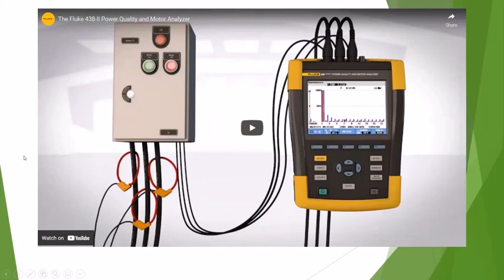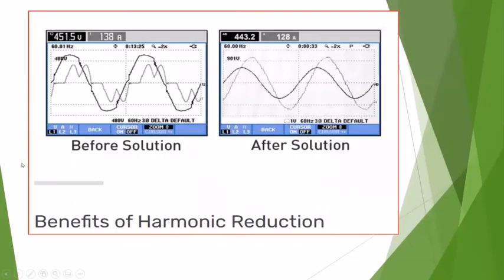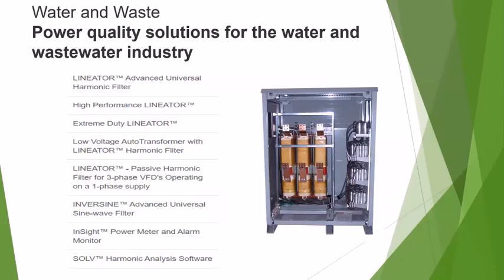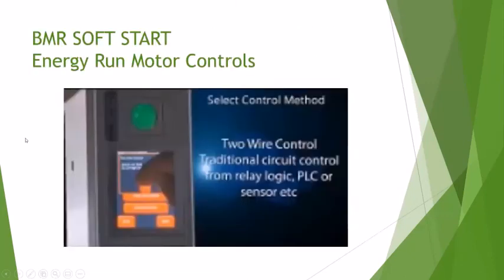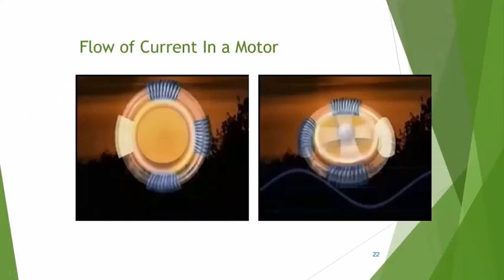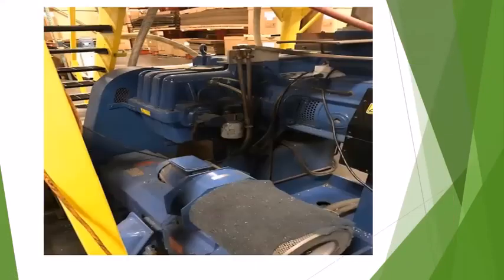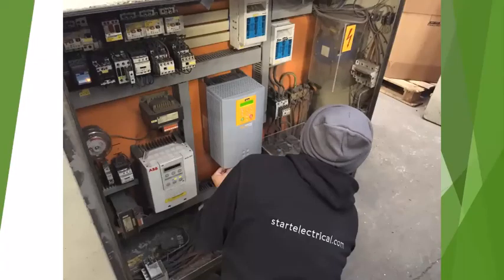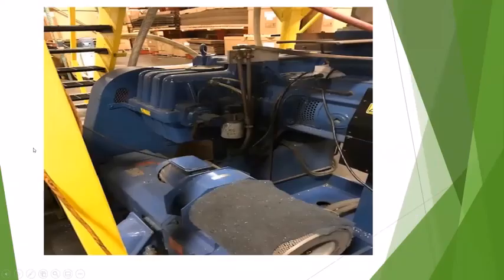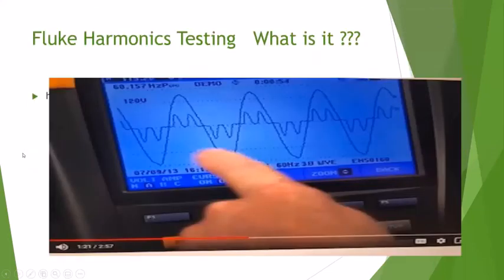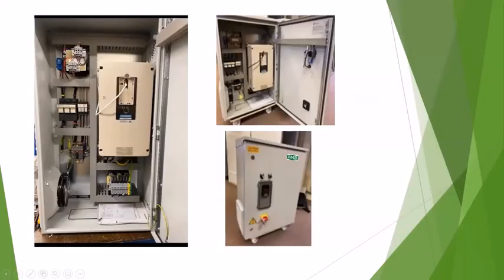But that's what I like to do. As my dad always said, keep it simple. A lot of people want to say, okay, I want to put a harmonic filter on, whatever. I like to go find out what the source is actually doing and really see what the effect is, because motors and loads and torques are all inherent in that ultimate value. We can either do the individual drives or we can do the package system, ready to go. So if you need the harmonic filtering, reactors and those things to keep it extremely clean, we can build those into the system also.